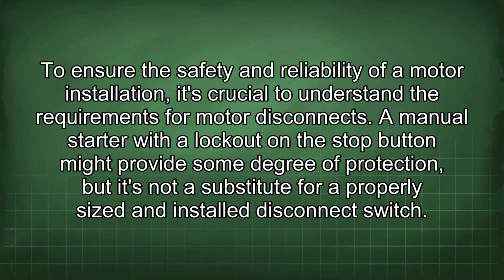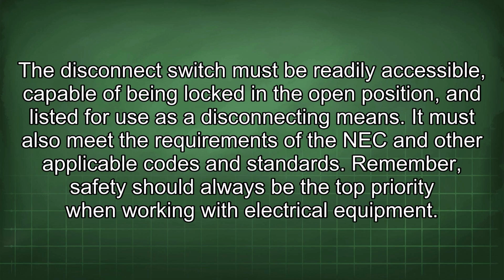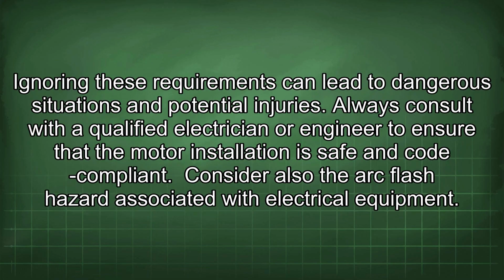A manual starter with a lockout on the stop button might provide some degree of protection, but it's not a substitute for a properly sized and installed disconnect switch. The disconnect switch must be readily accessible, capable of being locked in the open position, and listed for use as a disconnecting means. It must also meet the requirements of the NEC and other applicable codes and standards. Remember, safety should always be the top priority when working with electrical equipment. Ignoring these requirements can lead to dangerous situations and potential injuries. Always consult with a qualified electrician or engineer to ensure that the motor installation is safe and code compliant.